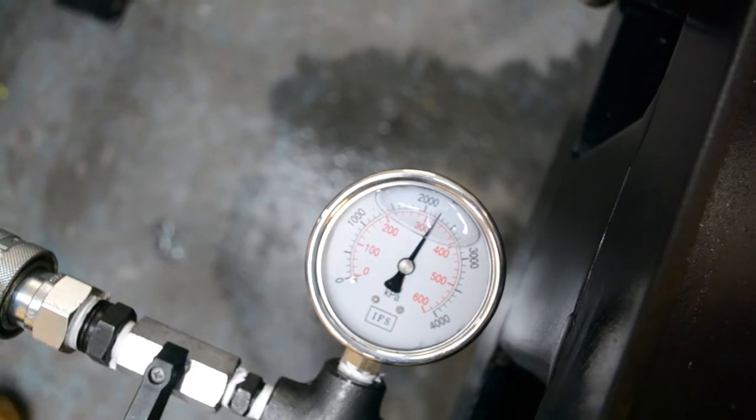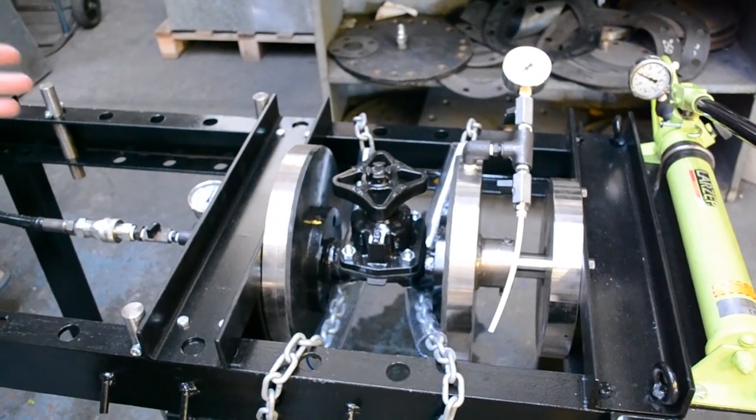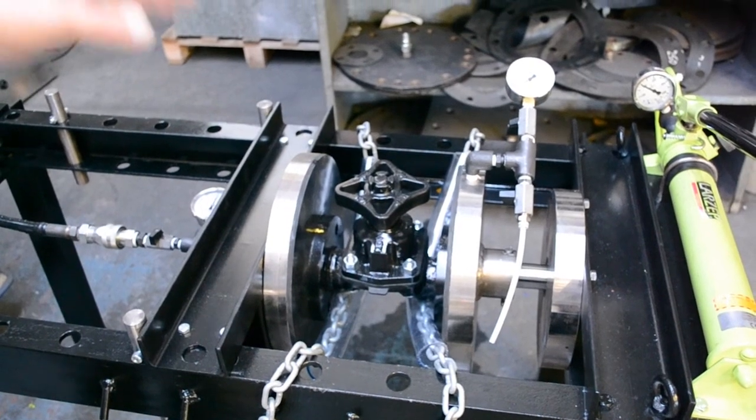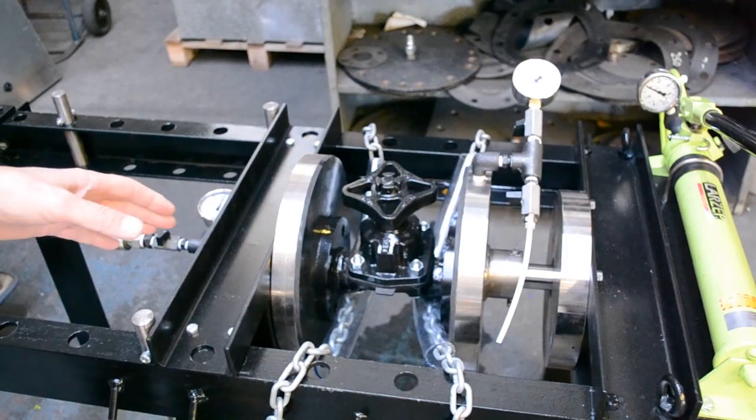Close the inlet pressure gauge valve. Visually check the valve for leaks and observe the gauge for pressure change. If no leaks are evident and the gauge remains static, the test valve has passed the shell test.